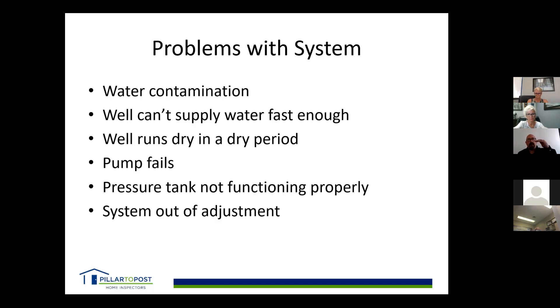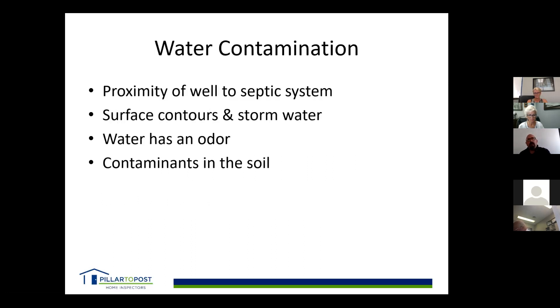Pressure tanks not working properly are easy to diagnose — if water from the tap goes fast-slow-fast-slow, it's usually the pressure tank that needs to be adjusted, not necessarily the pump. Pressure switches need balancing — you don't want the pump turning on at 20 psi and off at 80 psi, as that's a big fluctuation. Contamination is also a concern: proximity of the well to the septic system, surface contours, and storm water all matter. Well heads should be visible — they should stick out of the ground a minimum of 16 inches.